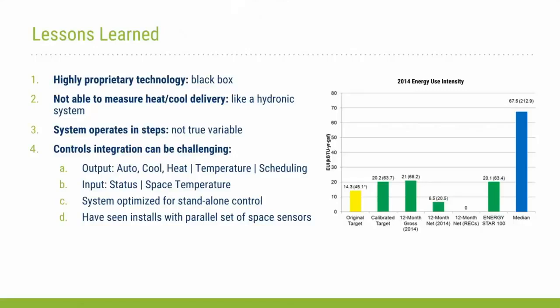Just the data on the right is our energy use intensity for the building. We originally had a target of around 15 for energy use intensity. After observing actual process energy use from the different agencies, this was adjusted up to approximately 20. The building in its first year, after some systems optimization, operated close to that target, and after considering the contribution of renewable energy, operated close to 6 for an EUI, so significantly less than a median courthouse office building for this climate zone. Next slide.